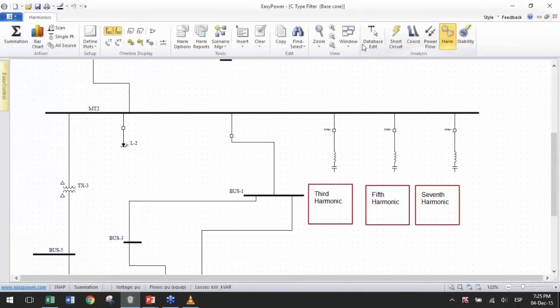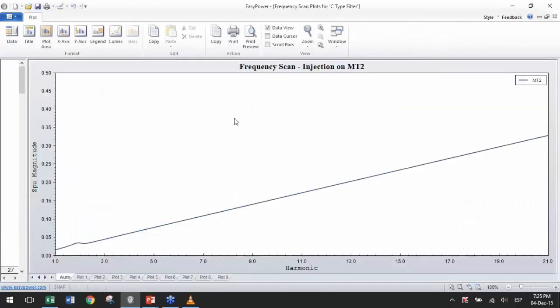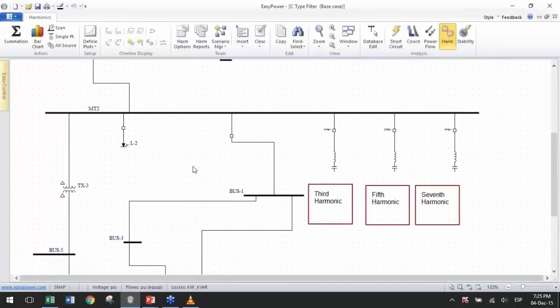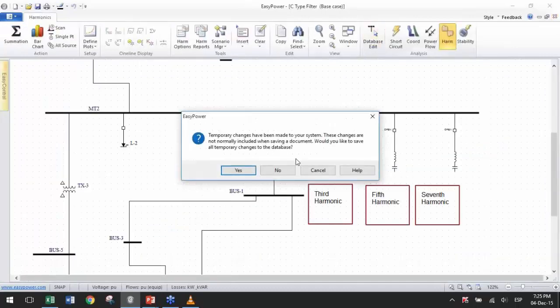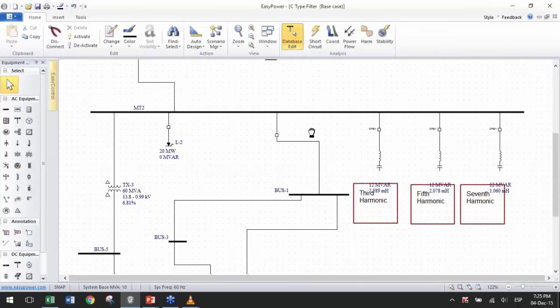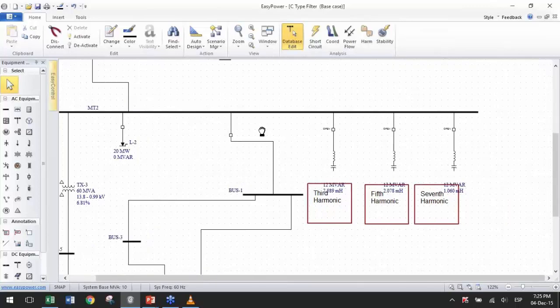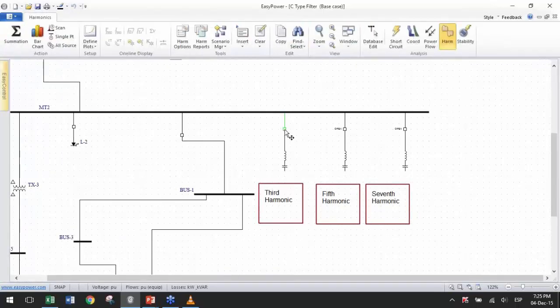So it's working as intended. It's providing a lot of reactive power, it's filtering the second harmonic, and it's attenuating the resonance. Now, these types of filters are recommended for lower order harmonics where notch filters don't work out so well. And the main use is second harmonic, yes. So, I guess that's it.